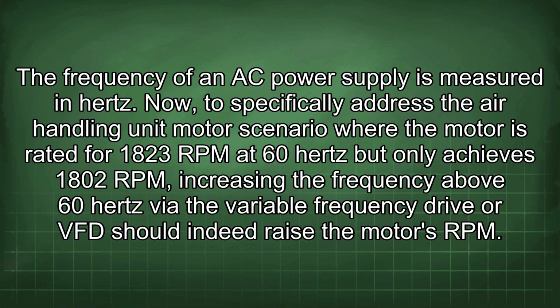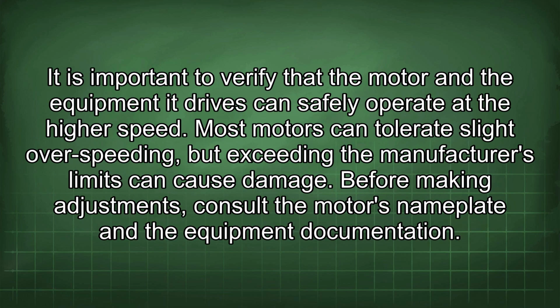Now, to specifically address the air handling unit motor scenario where the motor is rated for 1823 RPM at 60 Hz but only achieves 1802 RPM, increasing the frequency above 60 Hz via the variable frequency drive, or VFD, should indeed raise the motor's RPM. It is important to verify that the motor and the equipment it drives can safely operate at the highest speed. Most motors can tolerate slight overspeeding, but exceeding the manufacturer's limits can cause damage.